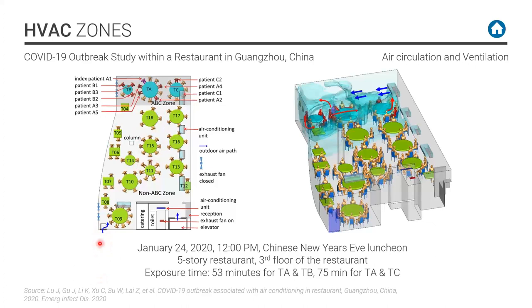There was an outside air connection over here where my cursor is. Probably just an opening in the wall or a damper. And they had wall-mounted VRF units that just pushed the air and recirculated it. So theoretically, the outside air would come in if you had an exhaust fan to draw it across. But what they believe happened is the amount of outside air that was here was a tenth of what the code requires and what we use in the States. And I speculate there was no outside air back here.